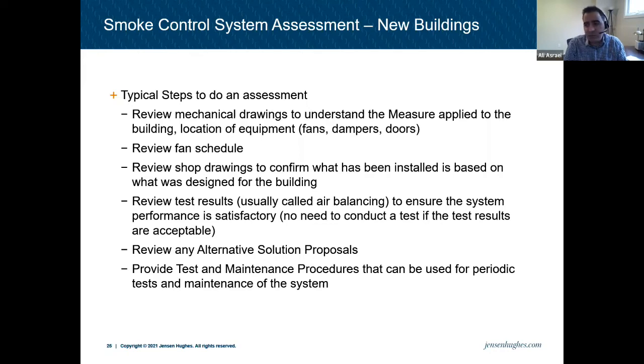So the other thing you need to do is review the shop drawings. This is to confirm that the fan provided by the contractor matches the design. Sometimes the designer asks for a 10,000 CFM fan, and somebody puts in the shop drawing an 8,000 CFM fan. They're like, okay, whatever, this is going to work. We don't have a 10,000 CFM available. Let's put 8,000.